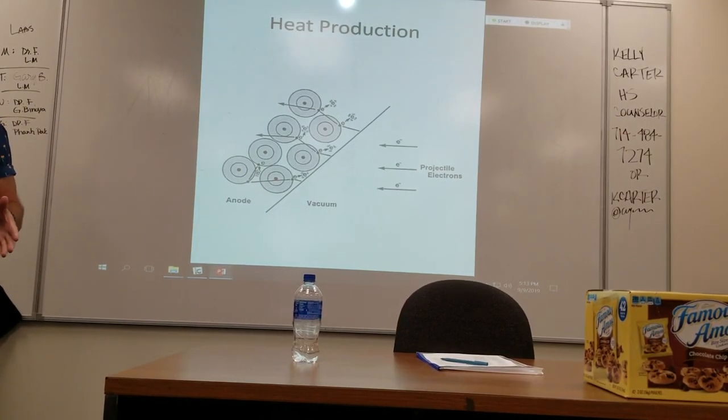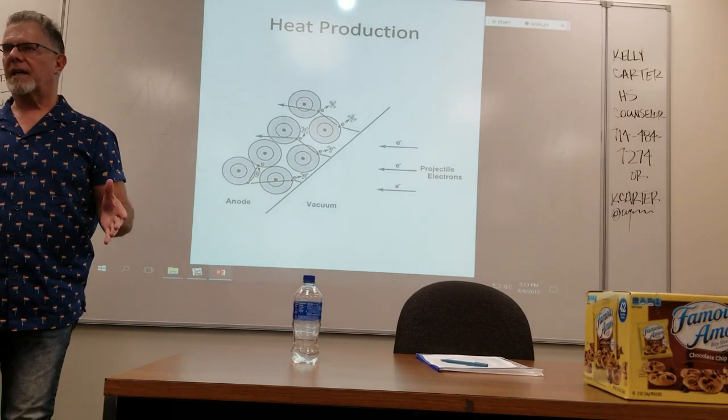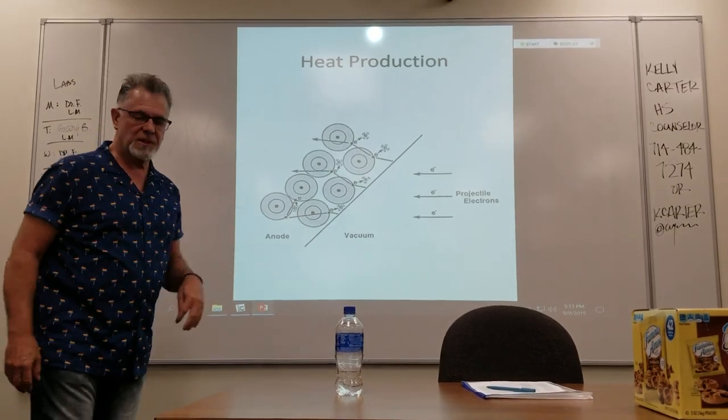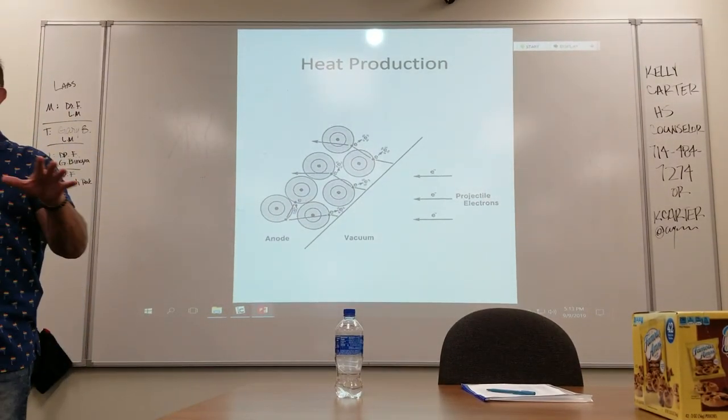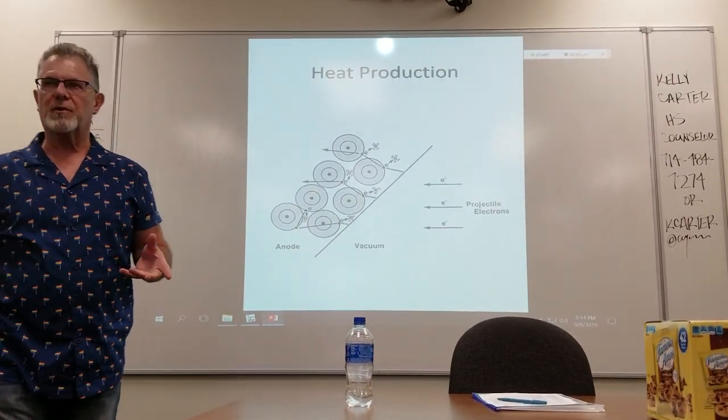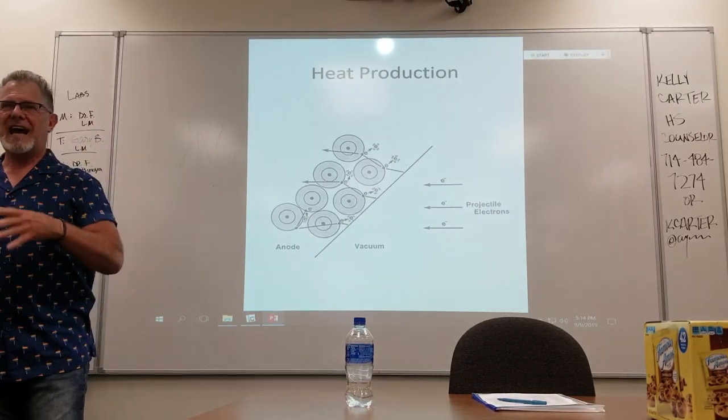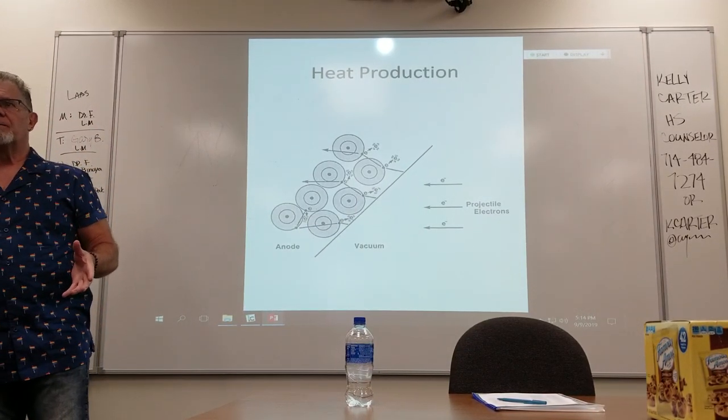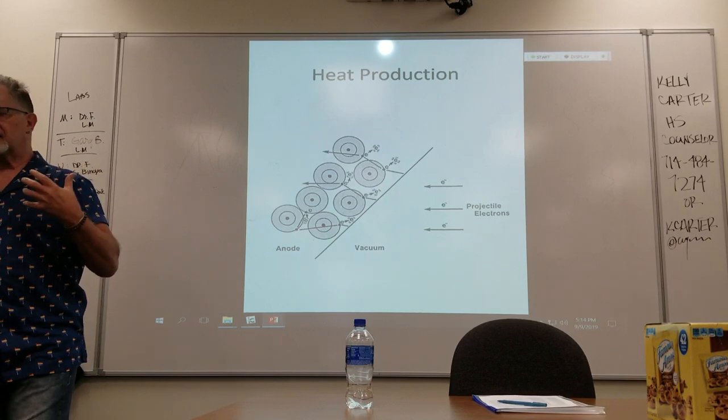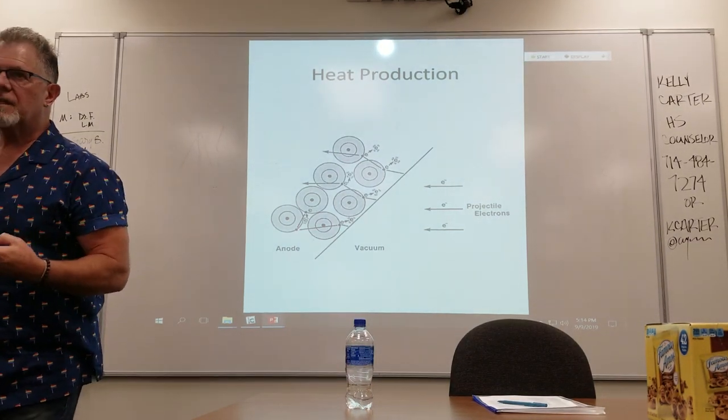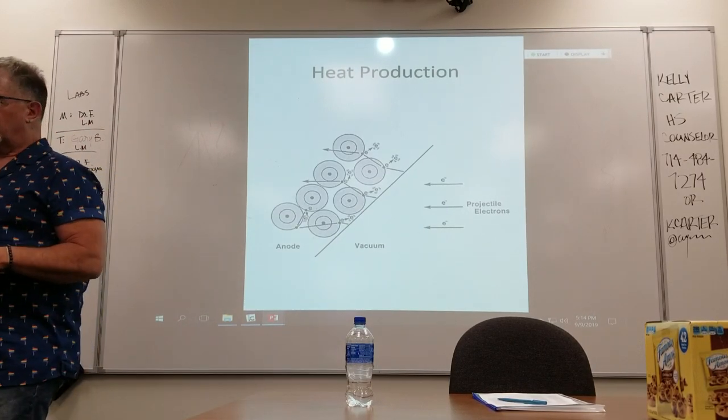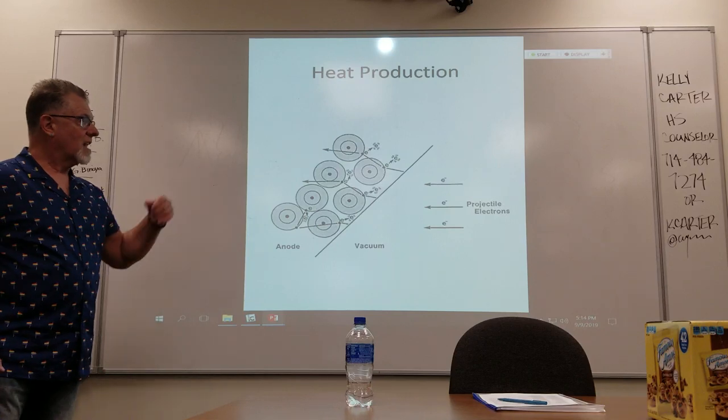Tube design has progressed incredibly since the early days. When I was a student we had two rating charts, you'd have two rating charts and all the documentation for the rooms you're doing. I doubt anybody here ever has to refer to those. New tubes have an incredible amount of heat loading. We had situations where we put enough heat into the tube that it fractured and broke, the tubes just weren't designed for it. But it's a whole new world. So, lots of heat.